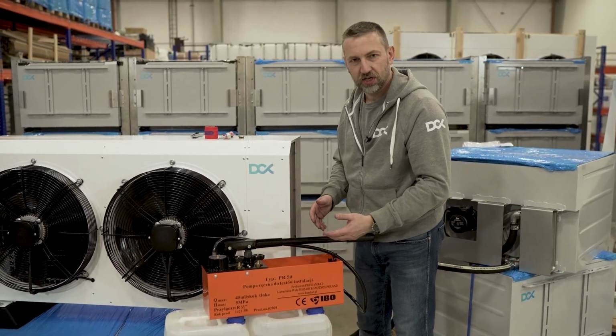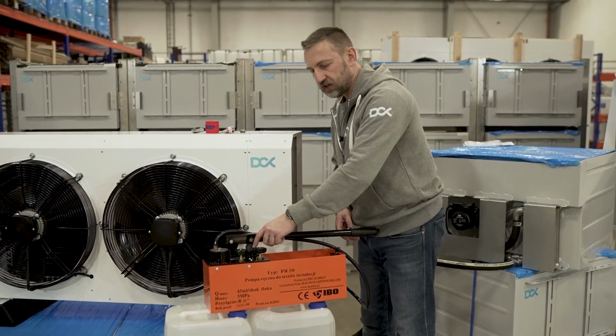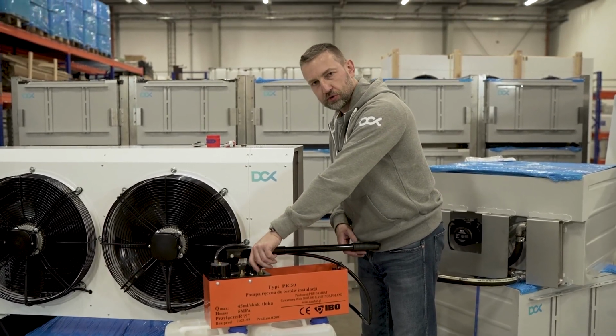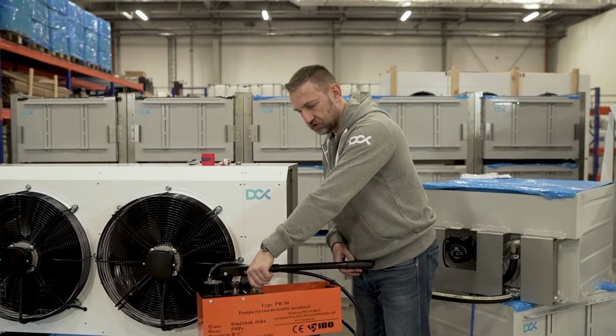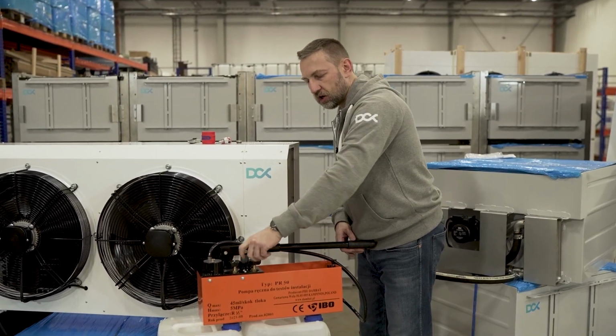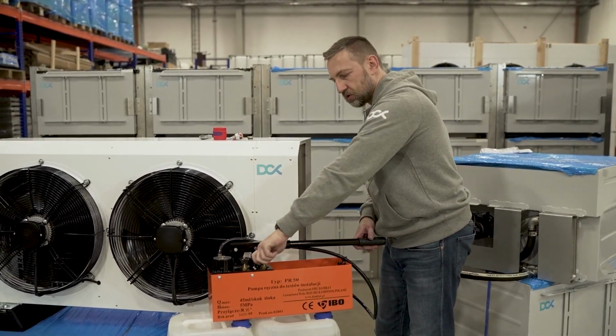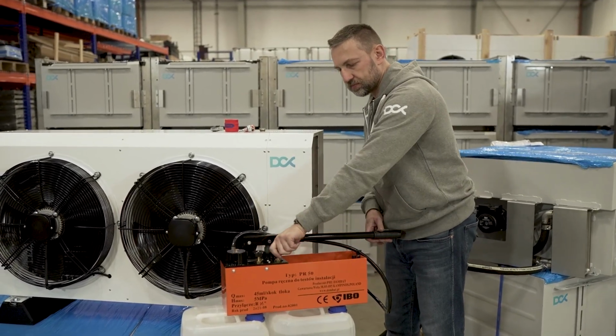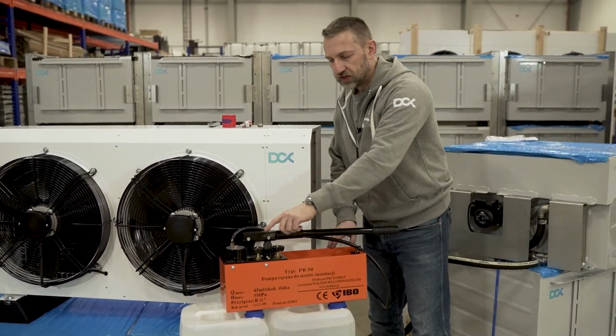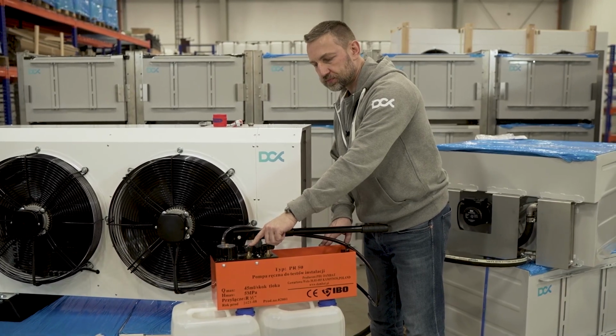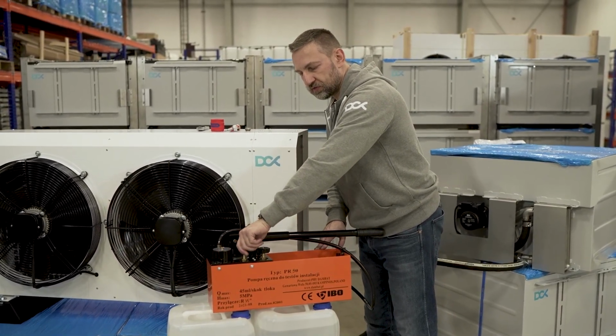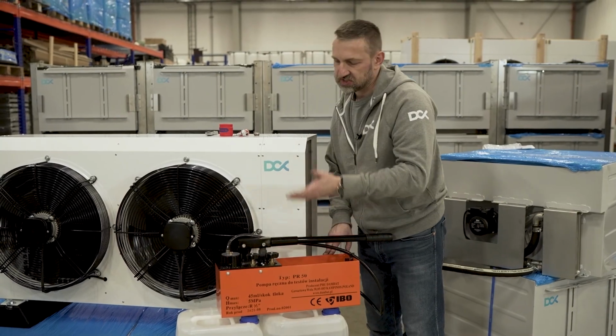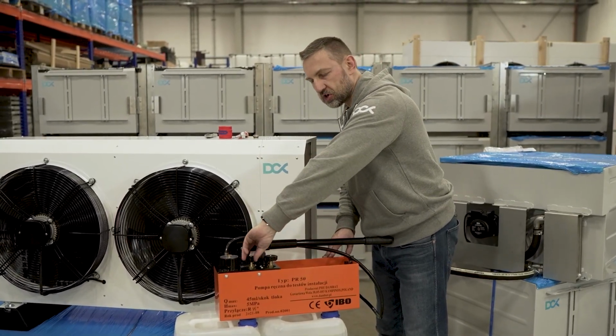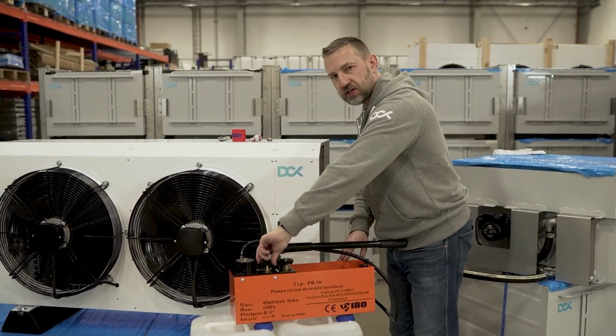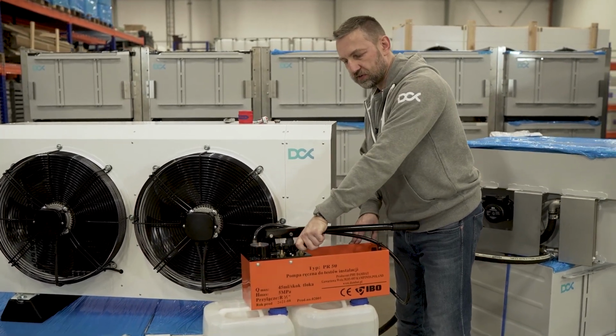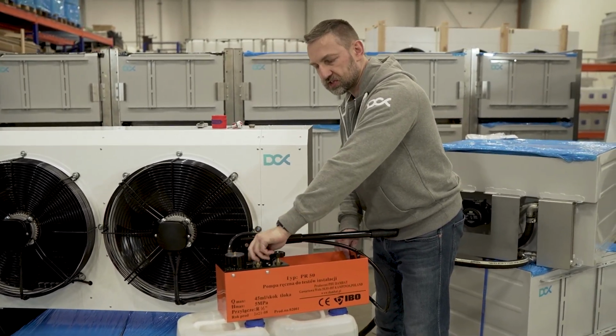If you feel that you added too much pressure to the system, you should open valve 2. For the filling procedure, I'm closing that clockwise. So turning right, clockwise. Now that's completely closed, right? Now I need to open valve 1 to be able to fill the loop. So I'm just opening it a little bit, to the left, counterclockwise, okay? So valve 2 is closed, valve 1 is open.